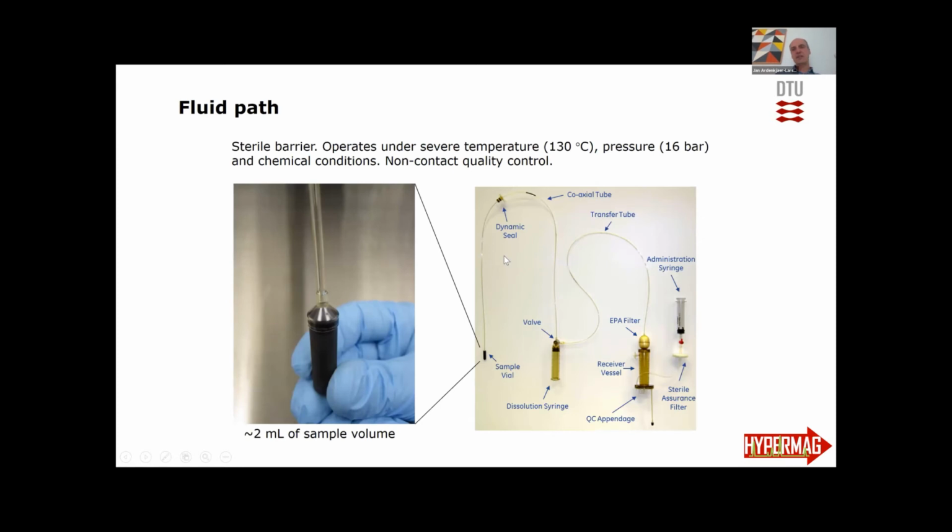One of the key inventions with the SpinLab was what we call the fluid path. So that's basically adopting concepts from nuclear medicine, where these sterile single-use cassettes are also very often used to contain the chemicals of the synthesizer for generating the radioligand.